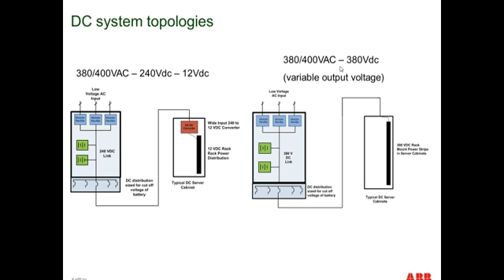Two such options are a little bit more scalable than the previous slide. The system that you see on the left, we've deployed successfully in many, many instances, utilizes a high-performance bulk rectifier, which feeds a 380 or plus minus 190 volt bus within a switchboard. Off of that switchboard on the lower left-hand side, you'll see we have a standalone battery charger, and the operational sequence of the system is pretty straightforward, and that's part of the beauty of DC. The batteries are diode isolated from the rectifier charger output. If the rectifier output voltage decays below the battery float voltage, the diode goes into conduction. Very simple system, very reliable system. The only challenge one has with it is the bulk rectifier is unfortunately a single point of failure. And again, the system has a variable output voltage on the bus, but highly proven technology.